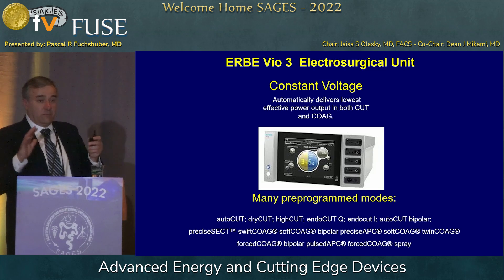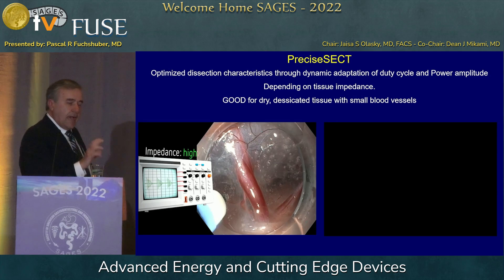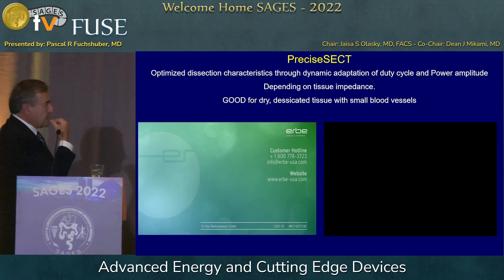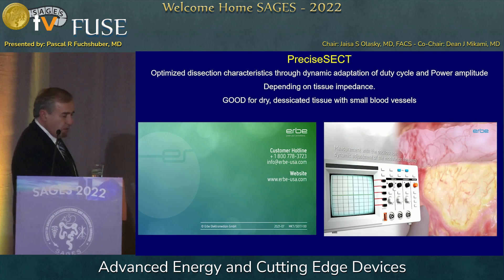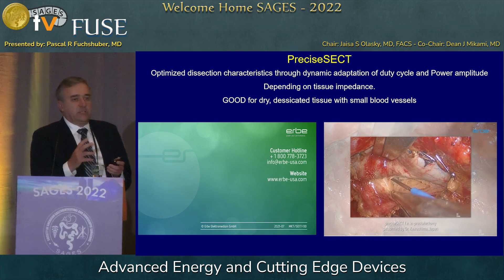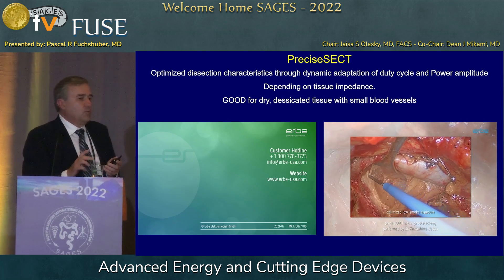I don't drive a complicated car — the newest car I drive is a 2002 — but for the young folks here, this might be your solution. I'm going to show you a quick video. It shows one particular program called PreciseSECT, which adapts the duty cycle. You can see on the oscilloscope that it adapts the duty cycle according to the impedance of the tissue. When it's low impedance, the duty cycle is wide; when it's high impedance, it narrows down. That built-in intelligence allows surgeons to not have to think too much about what the electrical energy is doing.